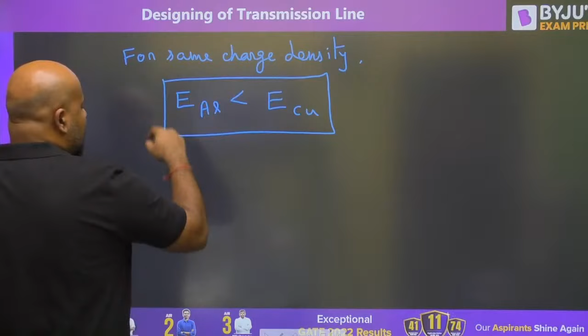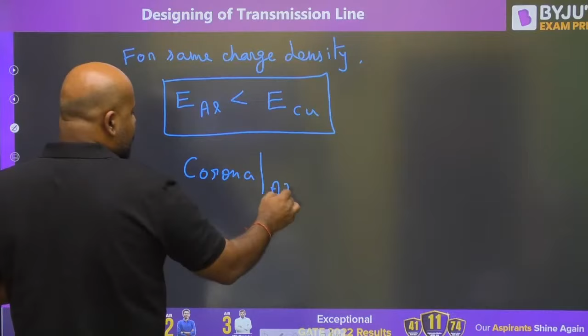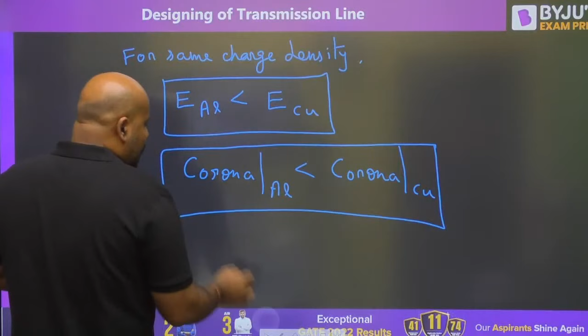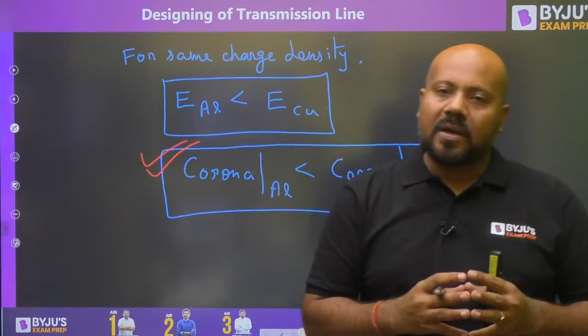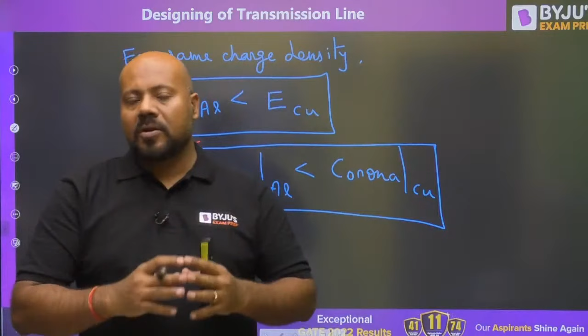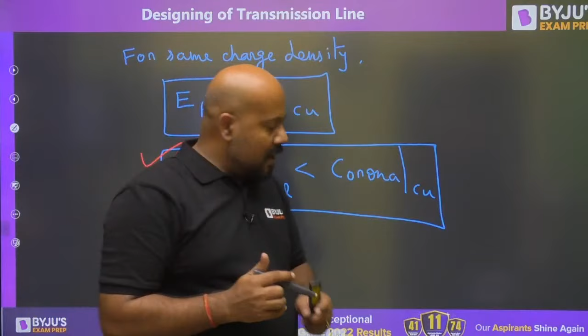So because of less electric field intensity, the possibility or intensity of corona - you must be aware of the corona phenomenon, if not, you can ask me - is going to be less in case of aluminum conductor compared to copper conductor. This is the main reason why we opt for aluminum over copper as a conductor material for designing our transmission line. So everybody who is live with me, just quickly tell me, are you able to follow this or not? If you are not comfortable with the corona phenomenon, I can give you some idea about it.